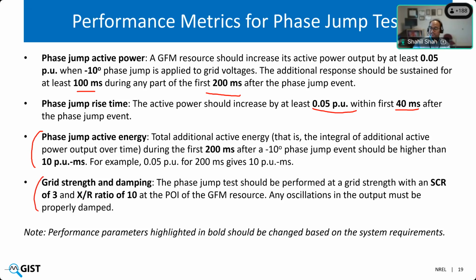So under what condition this phase jump should be performed. So with SCR of 3 and X by R ratio of 10. As I said, all the numbers in the bold, they are example values. A user can change these numbers depending on what are the system requirements. For example, if you are going to commission this grid forming resource in an even weaker grid condition like SCR of 1.8, then you would probably use that condition for checking performance to phase jump response.